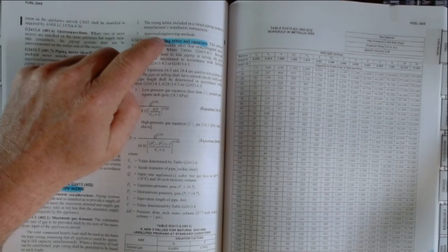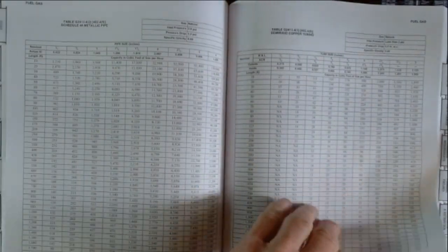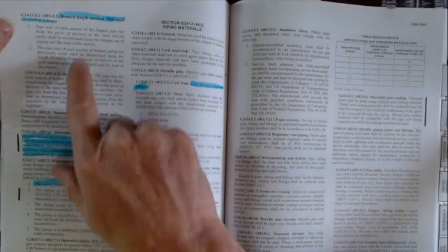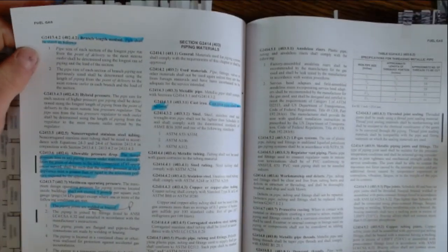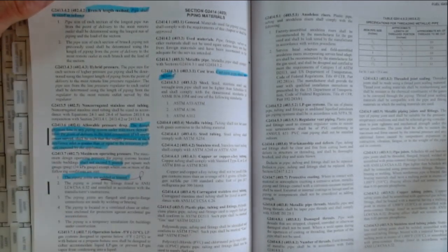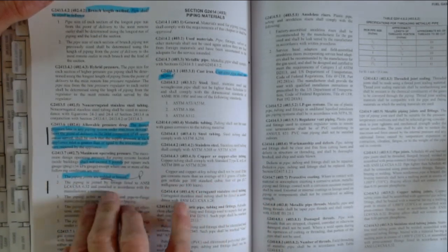No, the piping size methods. I think I was asked of these four, which is not the approved method. You have the sizing tables is approved, longest length method is approved. These are your sizing tables. They go forever here. And then the other third one is the branch length method. I think the one that was not allowed in that list was the appliance method or something goofy, some made up statement like that. 5 PSI for your gas lines. There's some allowances here and there. So cast iron pipes never to be used for gas lines. There's a bunch of prohibitions on gas lines you've got to keep in mind.